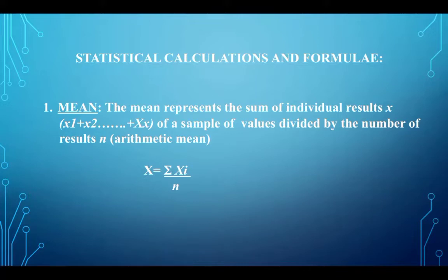The manufacturer's mean for 20 data points? Based on 20 data points, you will recalculate. But on day 1, which mean will be used by you? After 20 days, you have 20 data points. So now, one school of thought is you use the manufacturer mean and manufacturer standard deviation for 20 days. After 20 days, you will have 20 data points, and then you will start using your calculated mean and standard deviation. Correct, sir. Thank you.